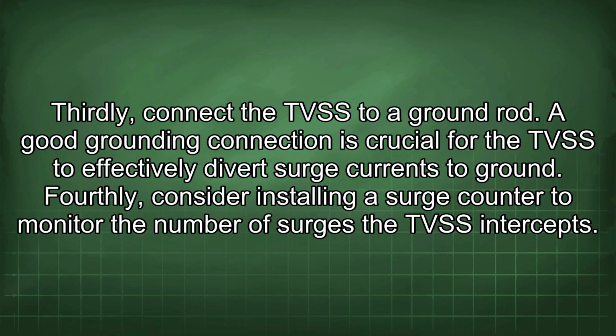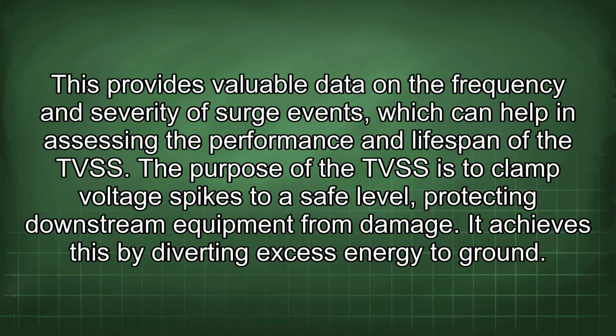Fourthly, consider installing a surge counter to monitor the number of surges the TVSS intercepts. This provides valuable data on the frequency and severity of surge events, which can help in assessing the performance and lifespan of the TVSS. The purpose of the TVSS is to clamp voltage spikes to a safe level, protecting downstream equipment from damage. It achieves this by diverting excess energy to ground.